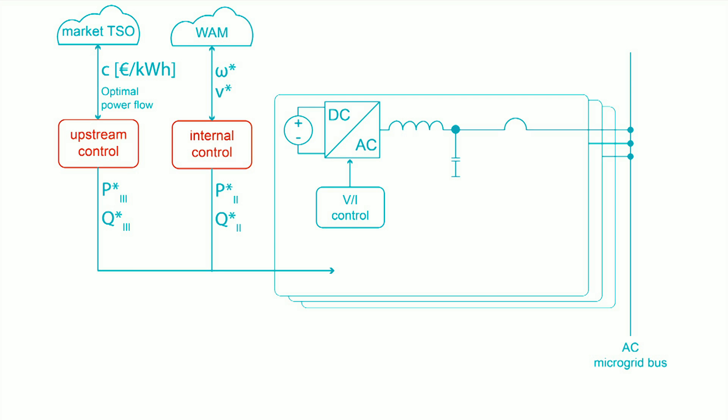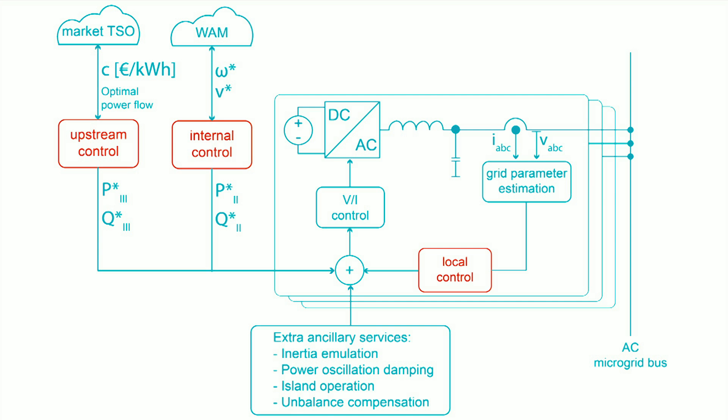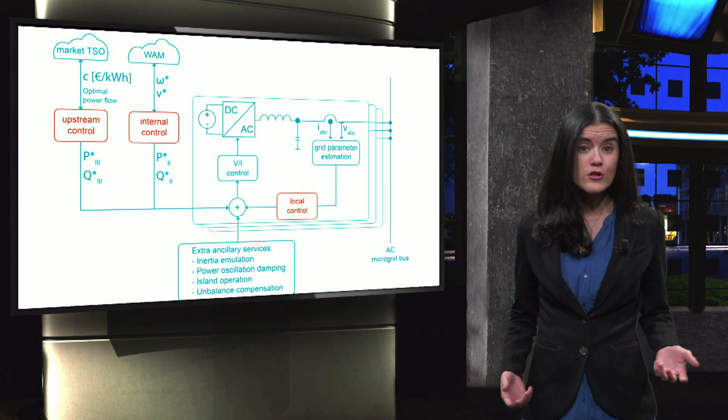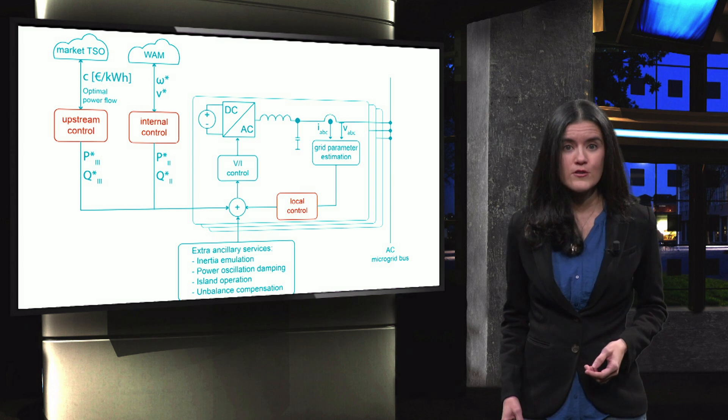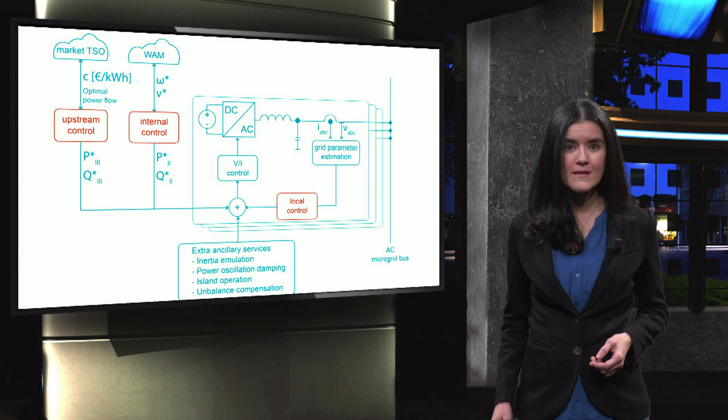At the lowest level, local control is implemented internally in a distributed generator in a decentralized fashion. Local control is the main responsible for controlling active power and reactive power in microgrids. The value of the three phase currents and voltages are retrieved from the grid and sent to the controller. A distributed generation unit might provide extra ancillary services to the microgrid. Inertia emulation is one of the typical ancillary services, as well as power oscillation damping, support island operation and power quality issues.